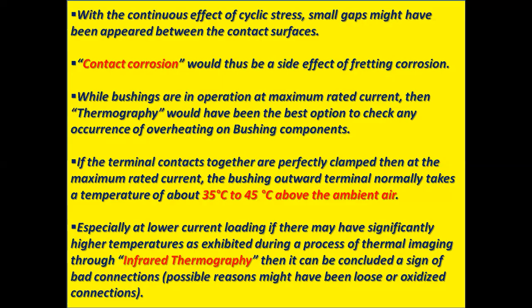Especially at lower current loading, if significantly higher temperatures are exhibited during thermal imaging through infrared thermography, then it can be concluded to be a sign of bad connections. Possible reasons might be loose or oxidized connections.